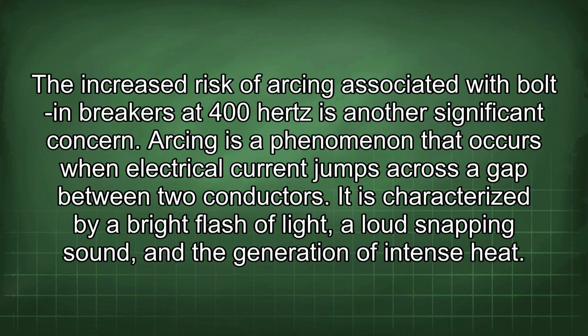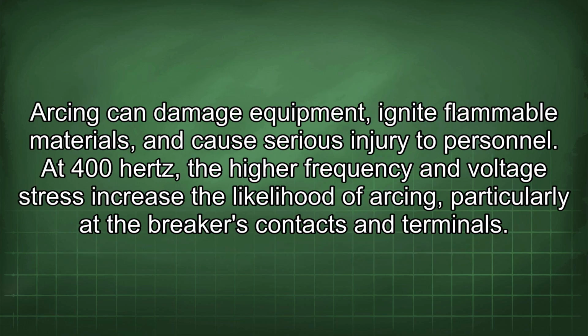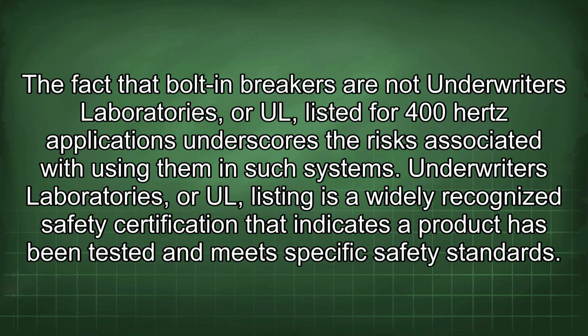The increased risk of arcing associated with bolt-in breakers at 400 Hz is another significant concern. Arcing is a phenomenon that occurs when electrical current jumps across a gap between two conductors. It is characterized by a bright flash of light, a loud snapping sound, and the generation of intense heat. Arcing can damage equipment, ignite flammable materials, and cause serious injury to personnel. At 400 Hz, the higher frequency and voltage stress increase the likelihood of arcing, particularly at the breaker's contacts and terminals. The fact that bolt-in breakers are not Underwriters' Laboratories, or UL, listed for 400 Hz applications underscores the risks associated with using them in such systems.